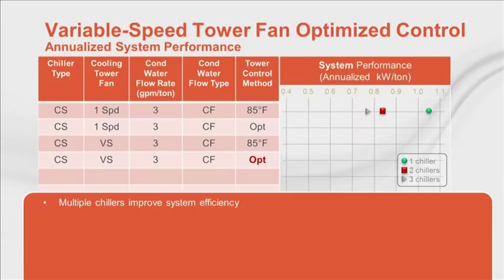This makes sense since the chillers themselves will likely operate in a more efficient mode, and ancillary energy consumed by constant speed equipment is much higher for 1 large chiller than it would be for 3 smaller chillers. Our next alternative only optimizes the cooling tower set point. We see that this reduces the annualized kW per ton about 0.1 in all cases.